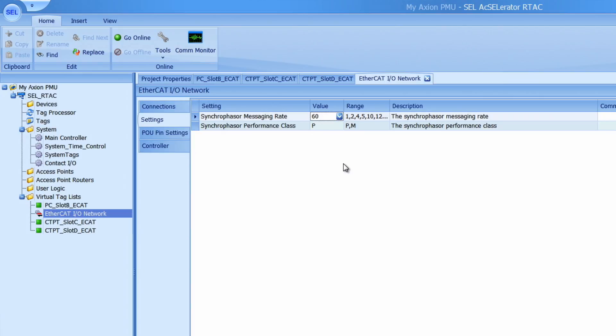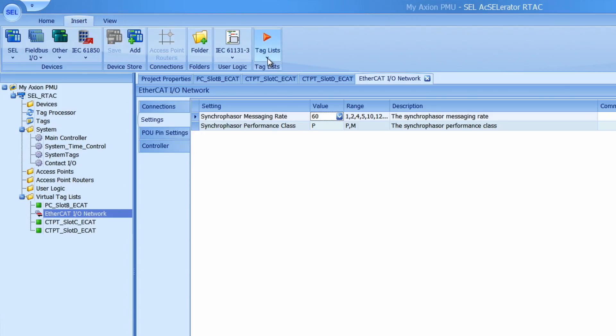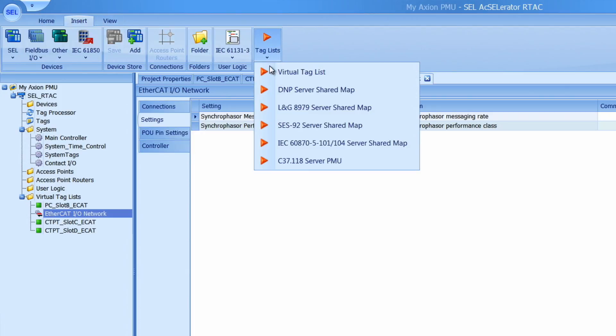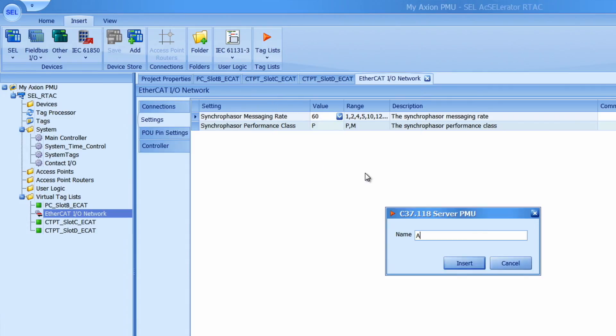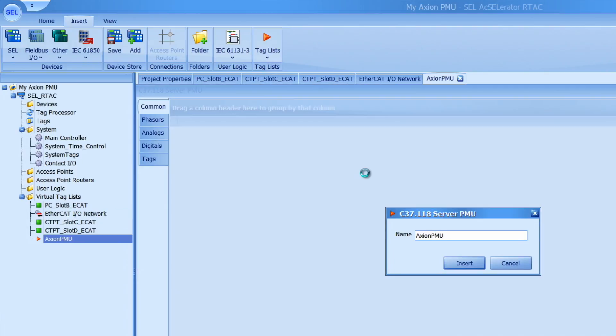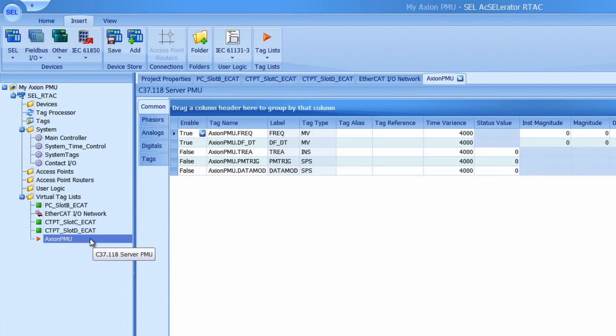The next thing we want to do is add a C37.118 virtual tag map that we will use to map the synchrophasor data into the C37.118 server. To create a tag list I can go to the insert tab and tag lists and then click on C37.118 server PMU. I'll call it Axion PMU. It will create the Axion PMU tag list in the left tree view over here.